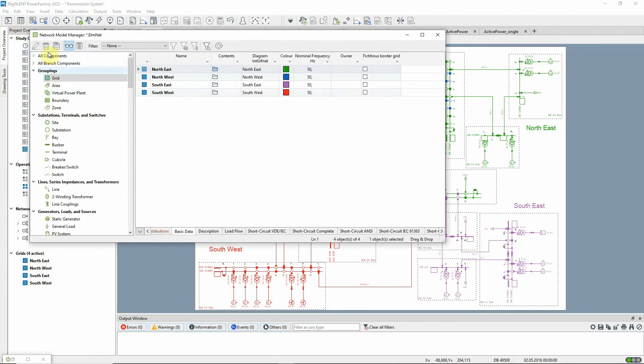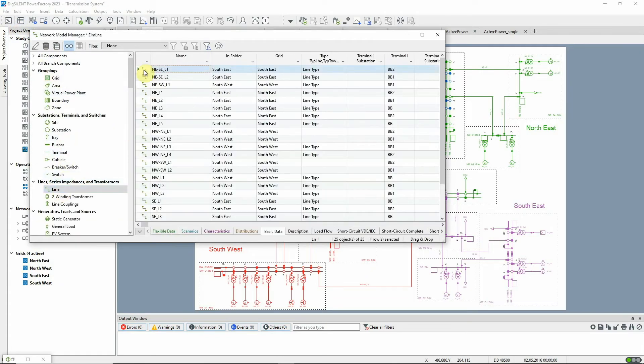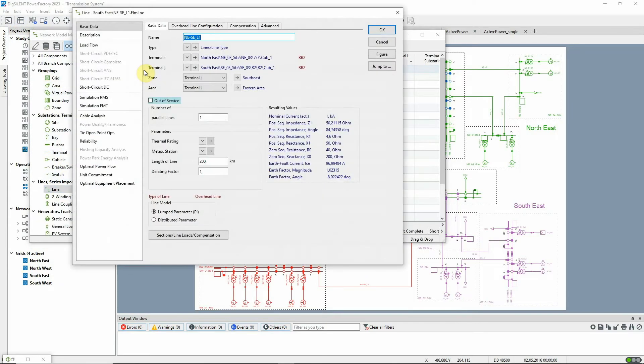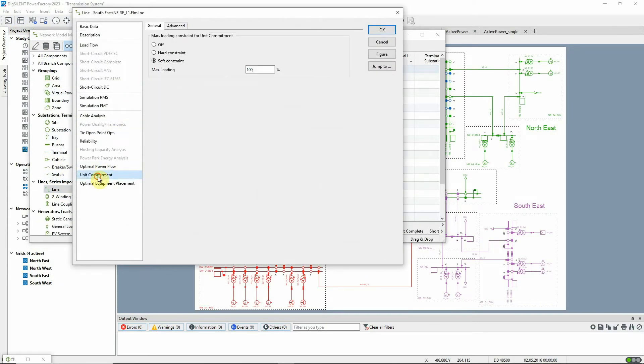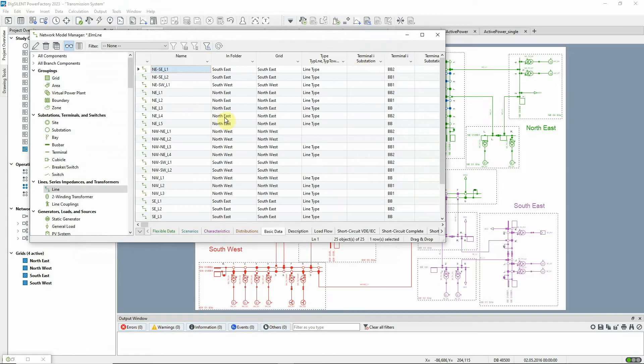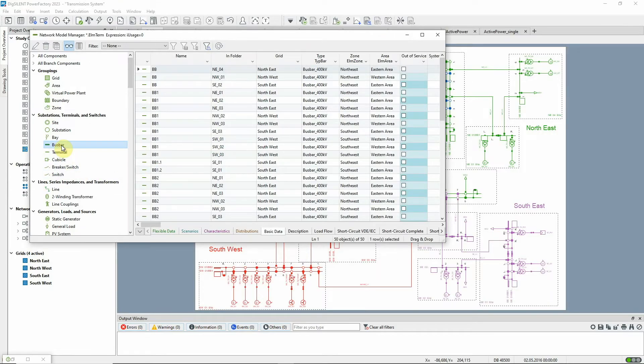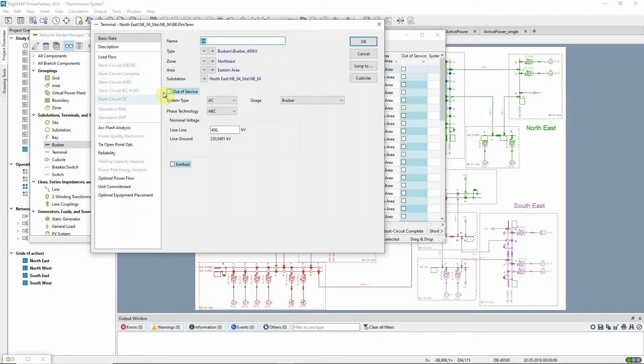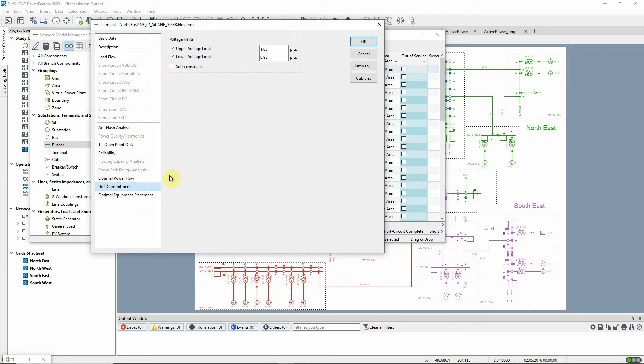In this example, we're considering branch flow constraints, which are set to a loading value of 100% for lines and transformers, and voltage constraints for main busbars, with a range between 0.95 and 1.05 per unit.